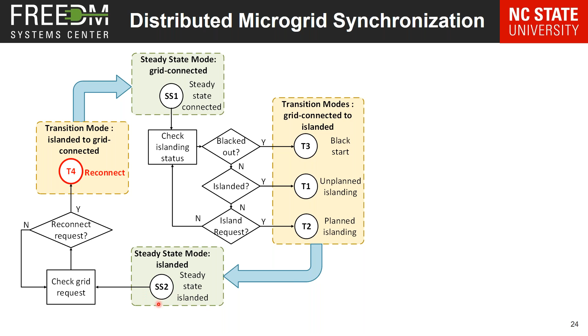So I described several of those islanded operations—resynchronization was one of those. This is a diagram of the decision tree, the logic tree for islanding: whether you've received a request from the grid, or it's not received a request, meaning it's an unplanned islanding status. In which case you need to operate in steady state mode as islanded, then be ready to reconnect when the main grid comes back.